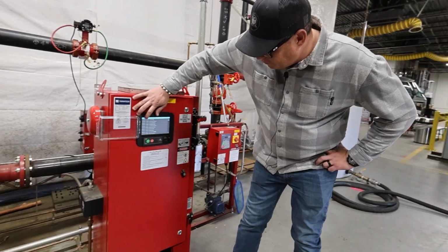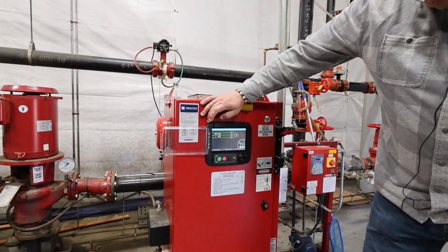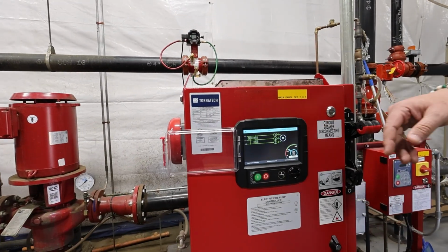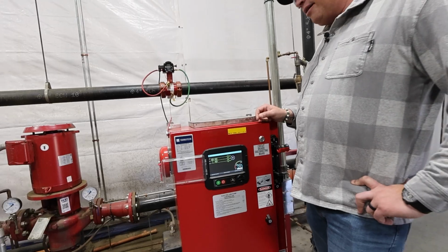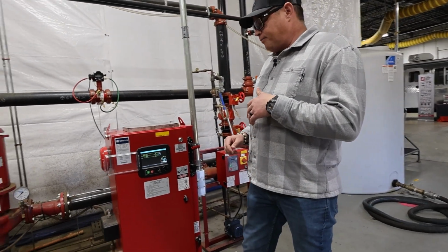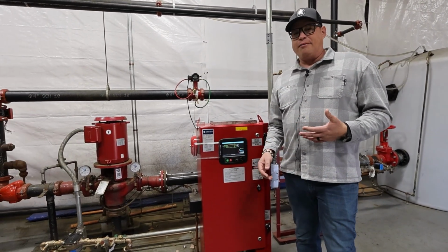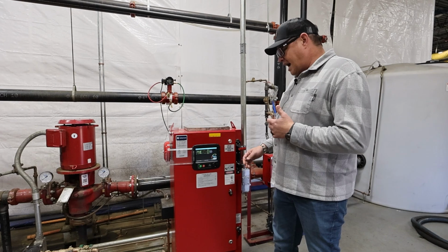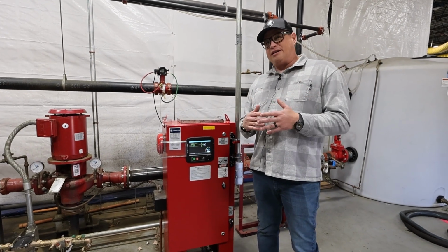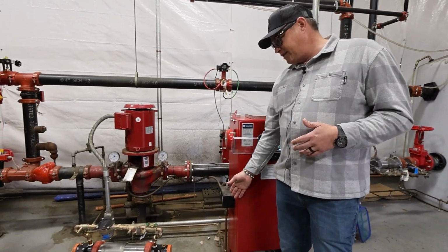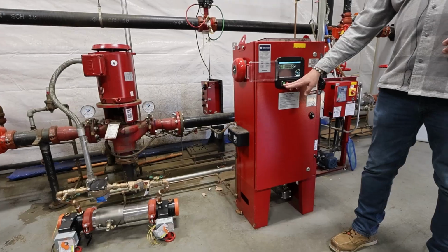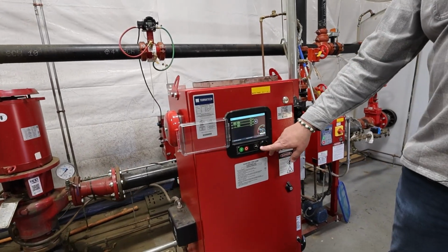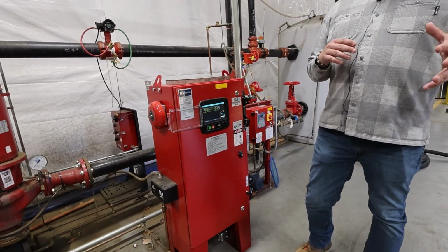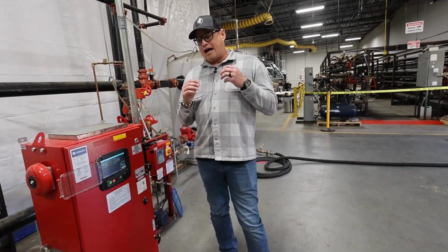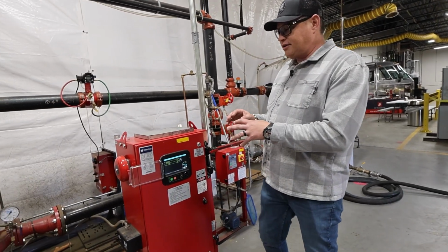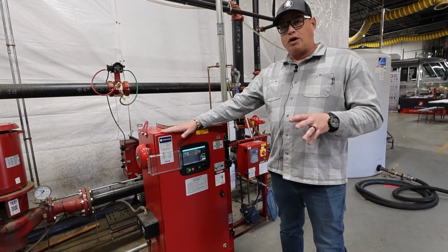So now we've gone through all that. I'm going to go back home, and I'm seeing that I've got proper power coming into my fire pump controller. There's multiple ways of starting a fire pump. I like to do every starting method possible, whether I'm dropping pressure from the sensing line, starting it manually with the start button, or using the run test button. I want to capture every device so that I know every starting device on this controller works properly.